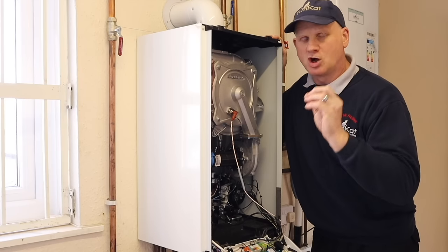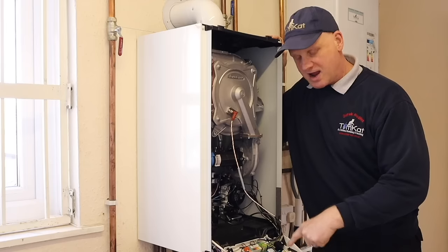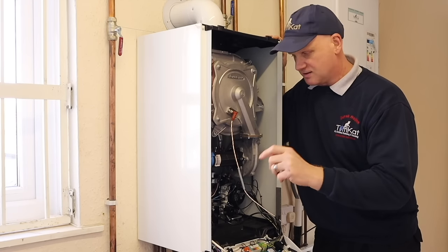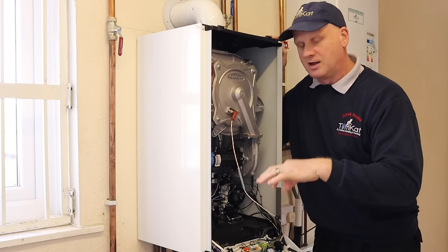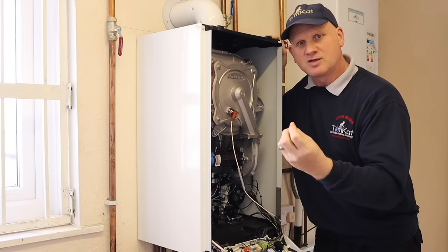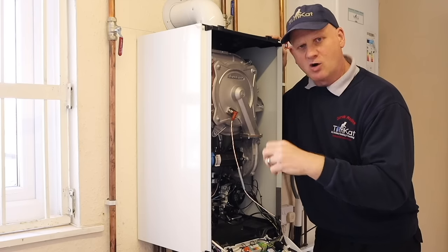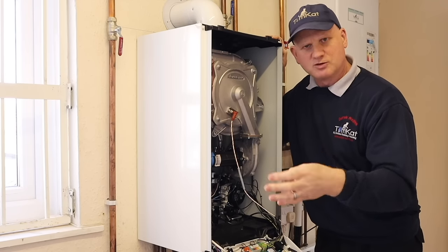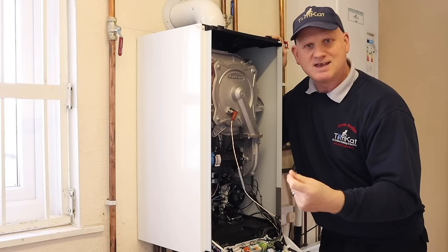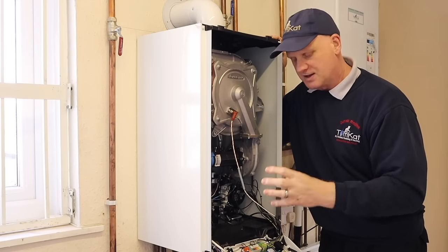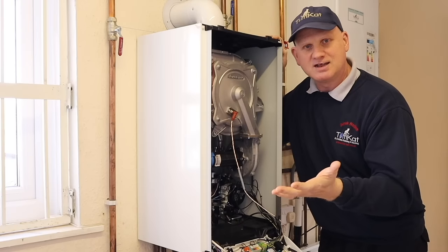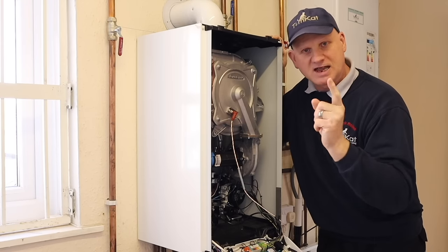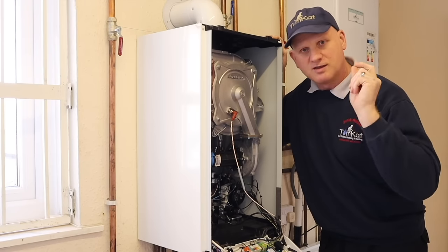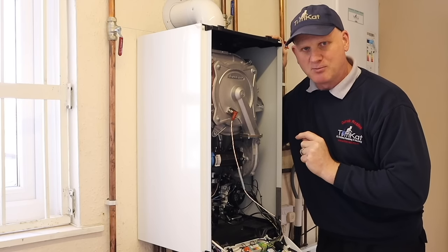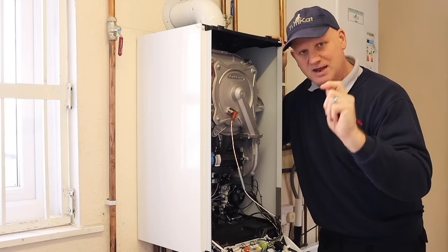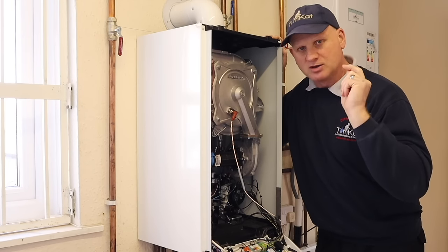Now, all boilers now are what's called modulating boilers. That means they have a computer brain in them. What the computer brain does, using thermistors, which regulate the flow and return temperatures of the boiler, is reduce the gas when the return temperature starts to get high. So when they initially start up, depending on whether you've got weather compensation, because what weather comp does is say, with the outside temperature, whether it needs to go into full burn or not, the brain will tell the boiler how much it needs to run. And it does that in these types of boilers by using the fan speed. The faster the fan goes, the more gas it draws into the boiler, the more energy that boiler's using. So the use of smart controls is incredibly important now to make the efficiency of these boilers at their best.